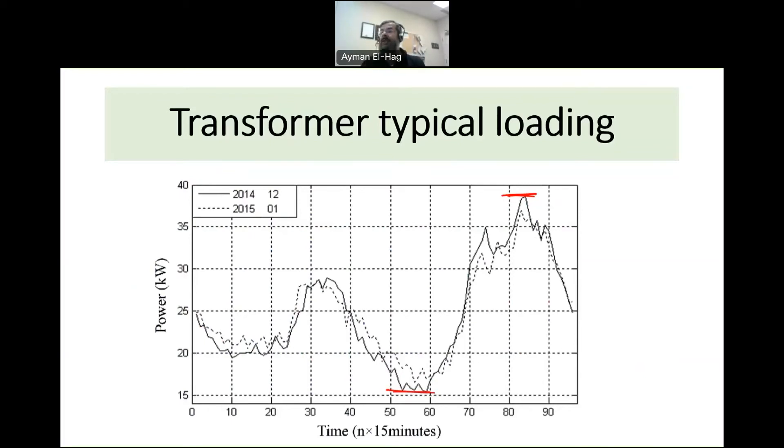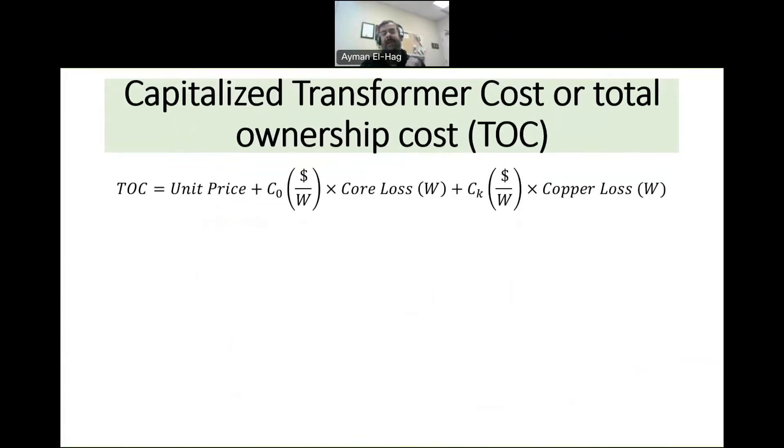Always the transformer is energized regardless if we have load or we don't have load, if we have a full load or a little load. Always the voltage is applied to the transformer 24/7, which means that the core loss is 24/7, unlike the winding loss which varies during the whole day.